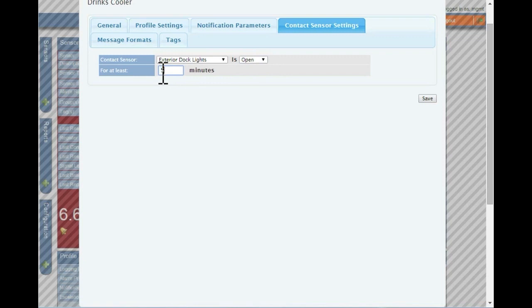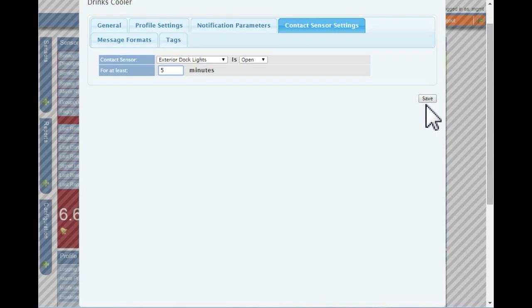Sometimes, it is useful to add a delay so that false alarms are not generated. In this example, we have decided that when the contact attached to a light is turned on, we will wait five minutes before turning our sensor on. Then, click save to update the information.